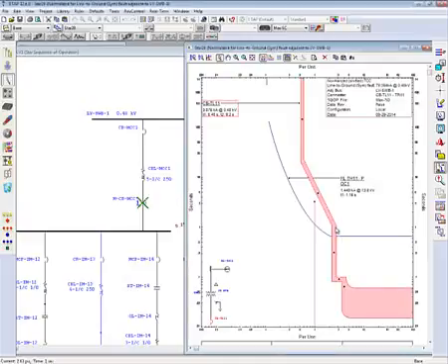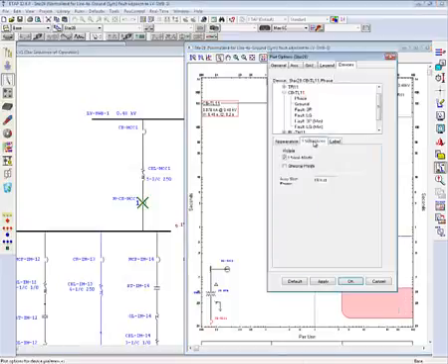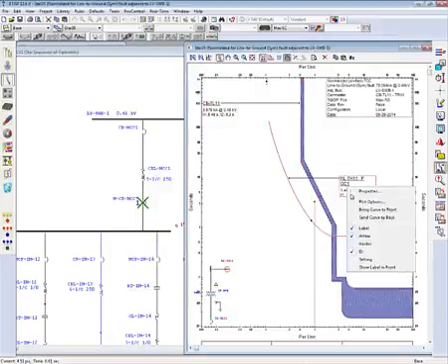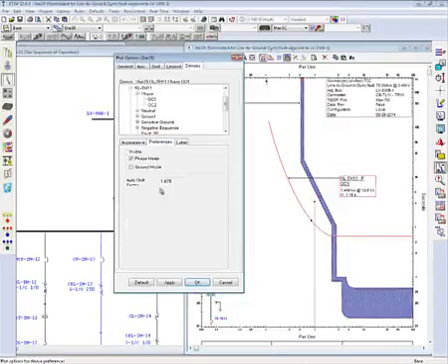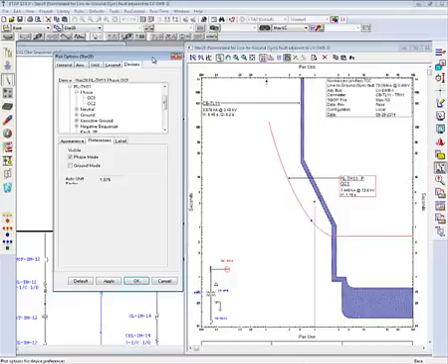These shift factors can be observed from the plot option preference page of the star view. So the shift factor for CBTL11 is 19.631 due to the through fault current through CBTL11, whereas the shift factor for the relay is 1.878 because of the through fault current through the relay. So different shift factors for different protective devices, based on actual fault conditions, will accurately depict the coordination between two protective devices.